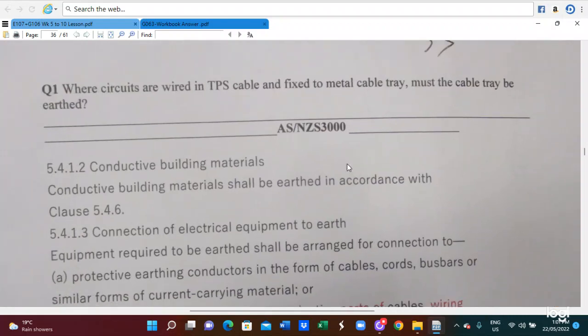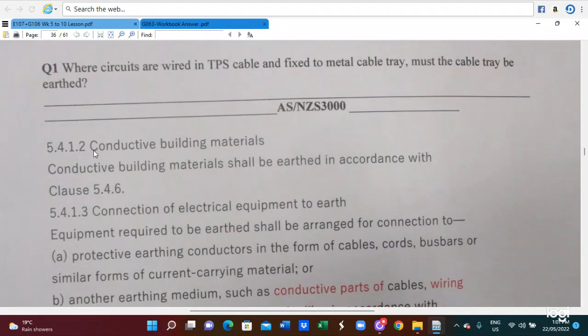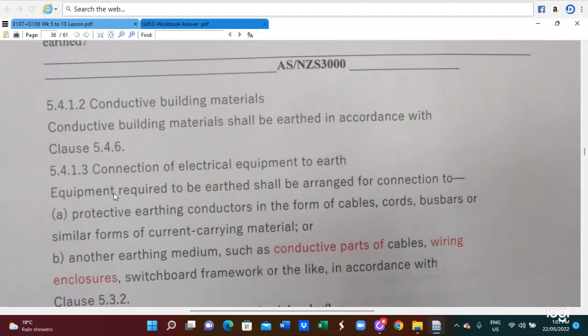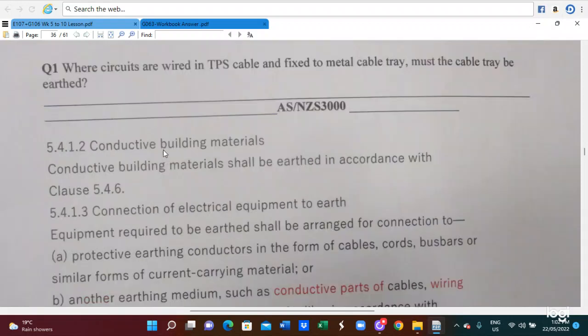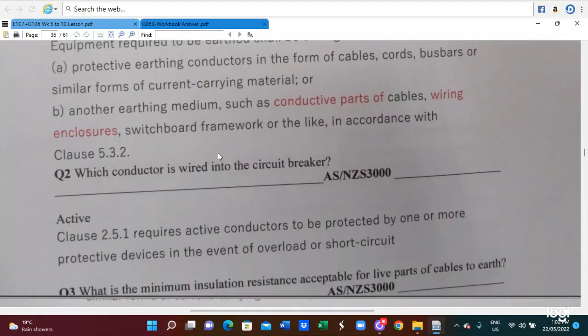So question one: where the circuits are wired with TPS cable and fixed to a metal cable tray, must the cable tray be earthed? In this case, we have to follow clause 5.4.1.2, conductive building materials, and we add a cross reference with clause 5.4.6. Clause 5.4.1.2 covers how to utilize the cable tray and how to do the protection.